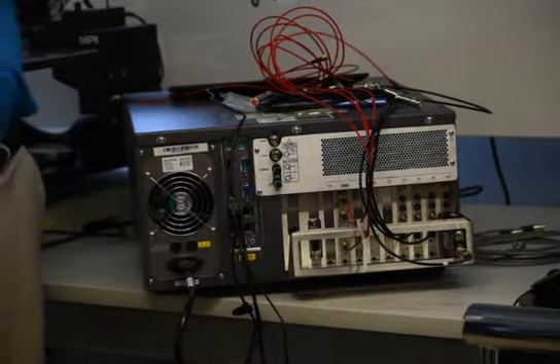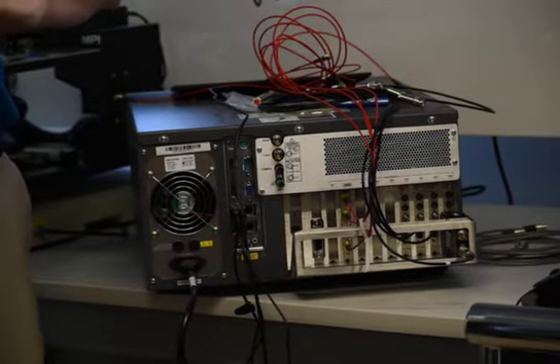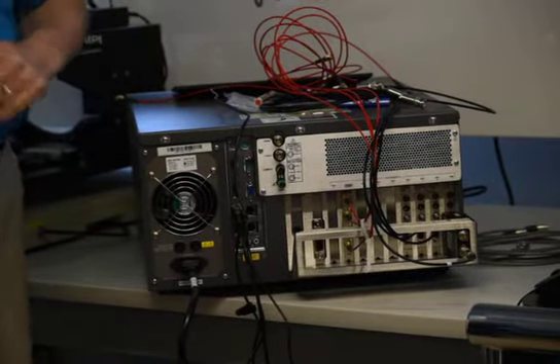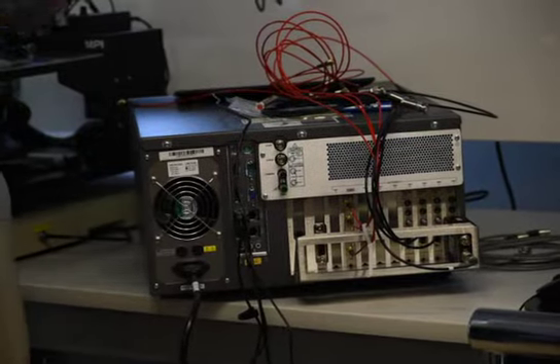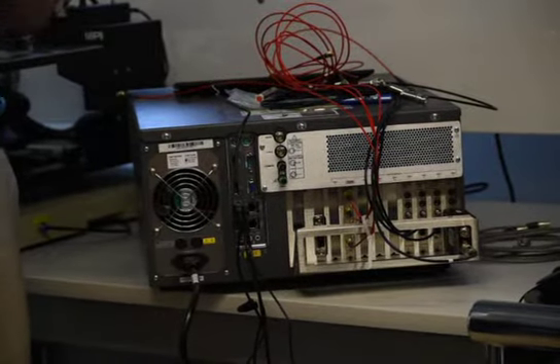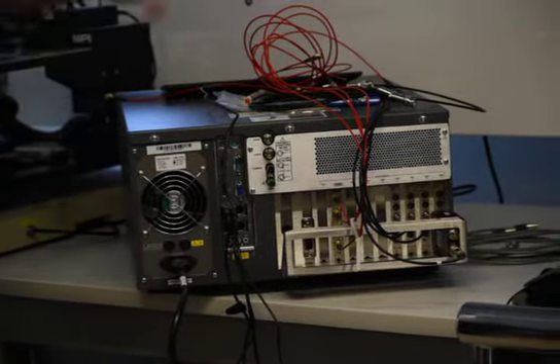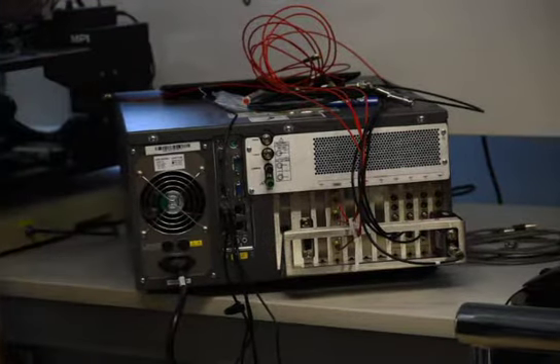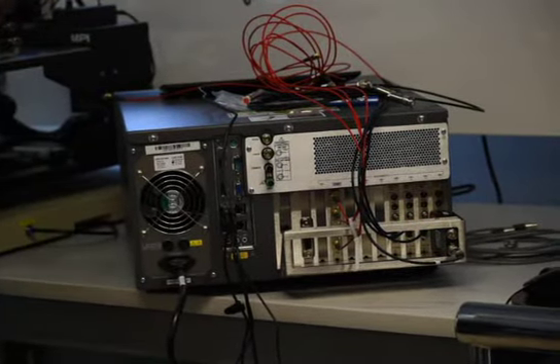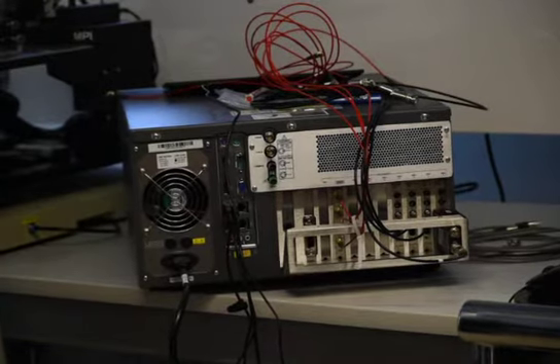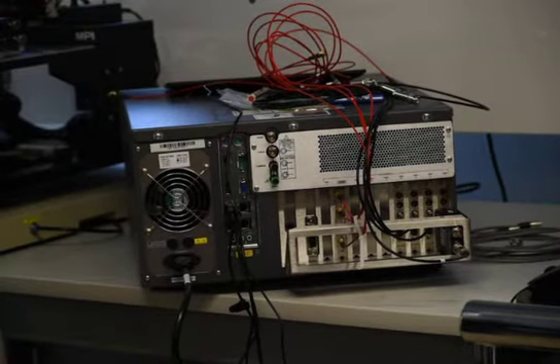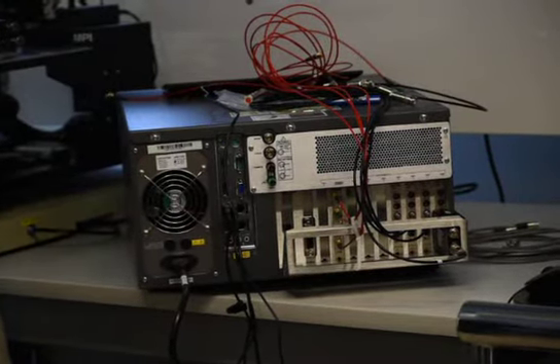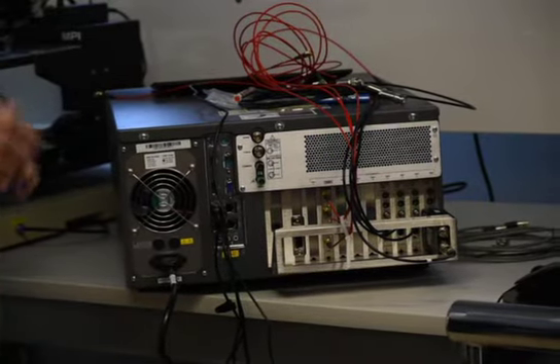Your highest accuracy is always on your lowest ranges. Since there are no ranges on the ground unit, it's not going to give you a great ground. It's okay, but it's not great. The other thing the SMU does is allow you to measure on that leg, where the ground unit doesn't. It just sources 0 volts, no measure. So if you ever select the ground unit, you'll see under measure it says NA. It won't let you.